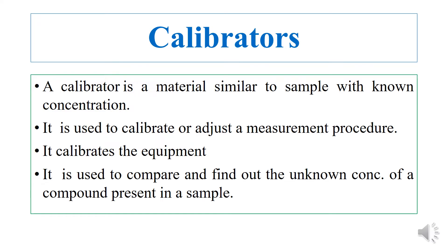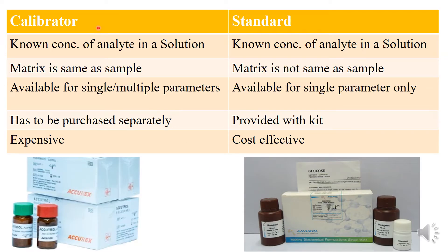So calibrators and standards are not the same. Let's look into the difference. Both have a known concentration of analyte in a solution, so they seem similar, but they are not interchangeable terminologies — they are not synonyms. The key difference is that the matrix of a calibrator is exactly the same as that of the sample, whereas for a standard, the matrix is not the same as that of the sample. The composition of the calibrator is exactly like that of the sample.